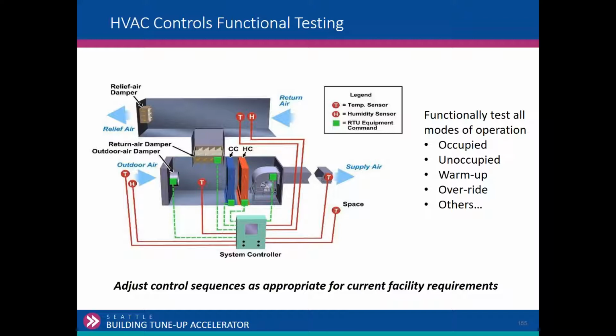So adjust the control sequence as appropriate for the facility. You know, if you don't have discharge air reset control, you don't need to implement discharge air reset control. It may be a good opportunity on a multi-zone system to do it, but that's a capital improvement. That's a controls project. And so we're just trying to get whatever they've got existing there to operate as efficiently as it can.